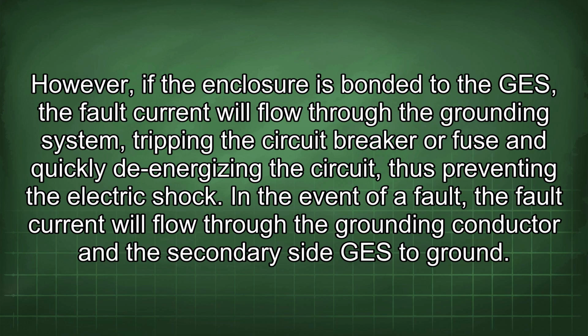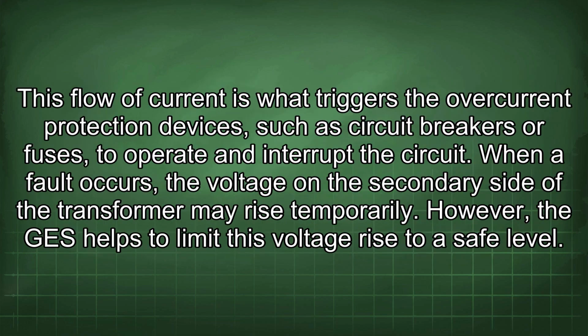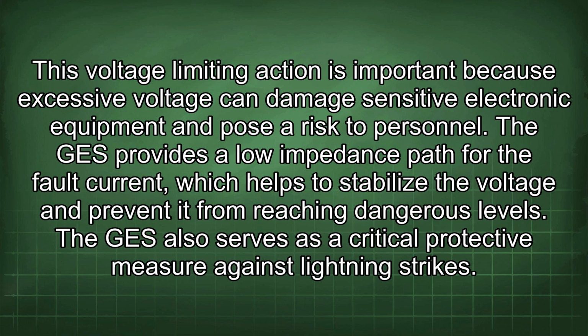In the event of a fault, the fault current will flow through the grounding conductor and the secondary side GES to ground. This flow of current is what triggers the overcurrent protection devices, such as circuit breakers or fuses, to operate and interrupt the circuit. When a fault occurs, the voltage on the secondary side of the transformer may rise temporarily. However, the GES helps to limit this voltage rise to a safe level. This voltage limiting action is important because excessive voltage can damage sensitive electronic equipment and pose a risk to personnel.